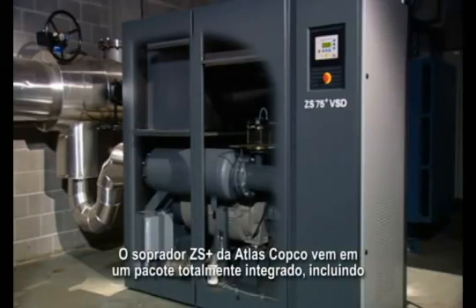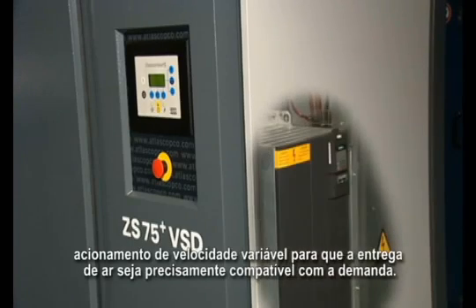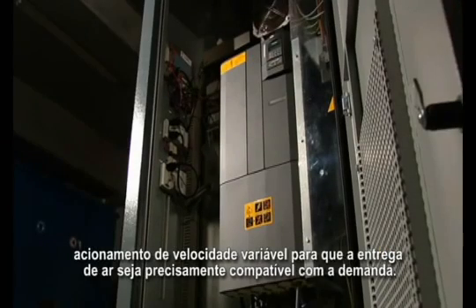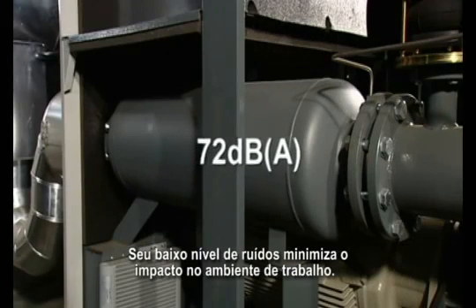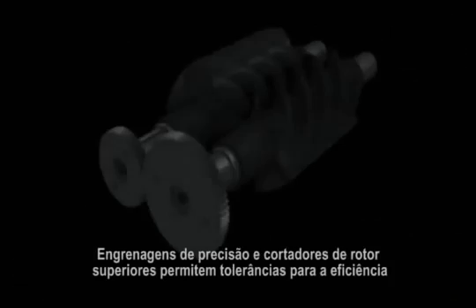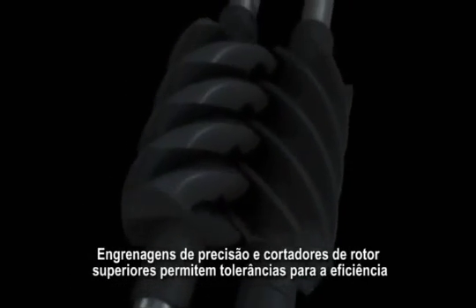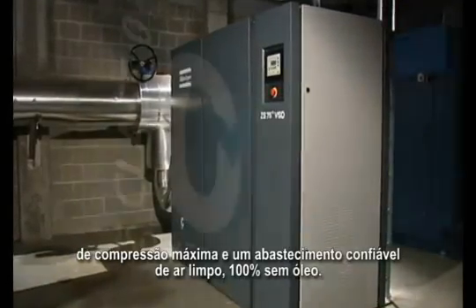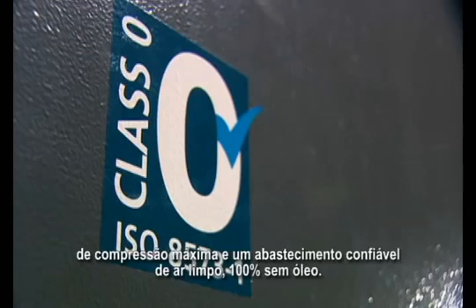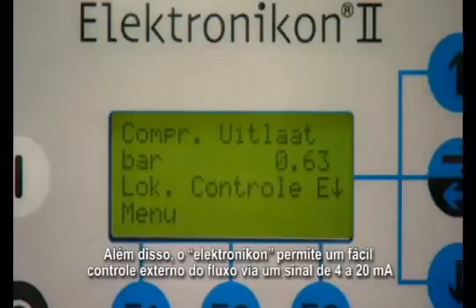The Atlas Copco ZS Plus blower comes in a fully integrated package, including variable speed drive, to precisely match the air delivery to the demand. Its low noise level minimizes the impact on the working environment. Precision timing gears and superior rotor coating allow close tolerances for maximum compression efficiency and a reliable supply of clean, 100% oil-free air. On top of that, the Elektronikon allows easy external flow control via a 4 to 20 milliamp signal.